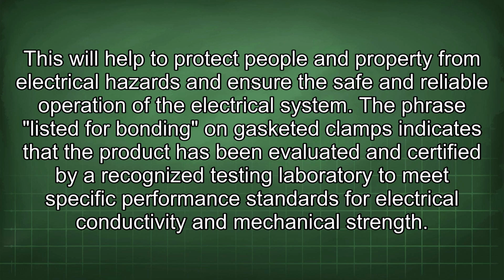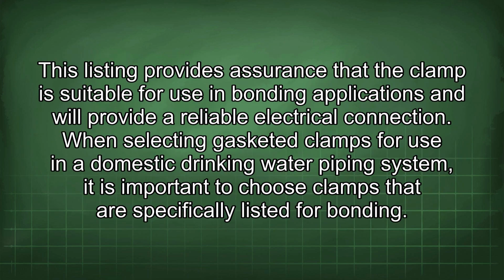The phrase "listed for bonding" on gasketed clamps indicates that the product has been evaluated and certified by a recognized testing laboratory to meet specific performance standards for electrical conductivity and mechanical strength. This listing provides assurance that the clamp is suitable for use in bonding applications and will provide a reliable electrical connection.